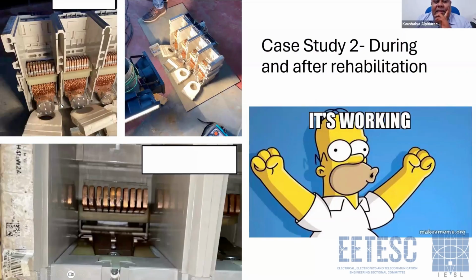Yes, this ACB can be completely disassembled. These are the inbuilt CTs of your ACBs, right? These will have to be replaced. We tried drying, but it was not successful, so we had to replace them. This was the drying process. After a thorough clean, it was dried, and now it's in operation, followed by replacing all the electronic parts. After the refurbishment, the APCL engineers and the other staff did the complete restoration and it is back in operation.